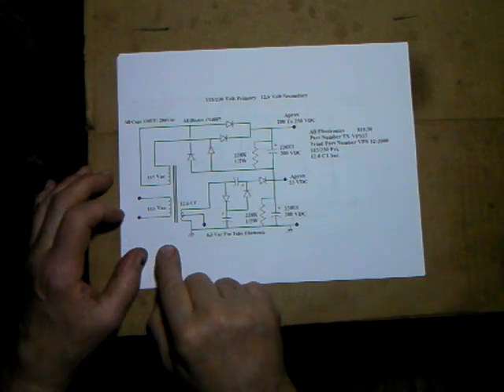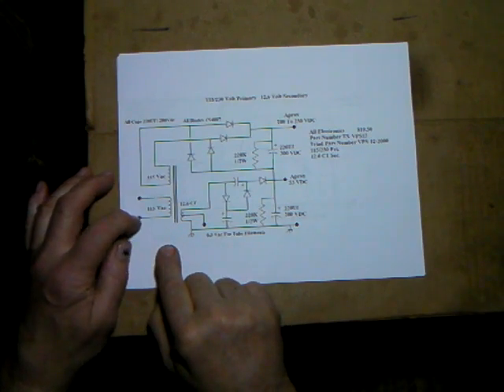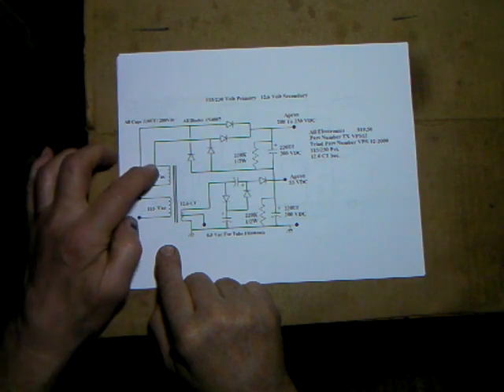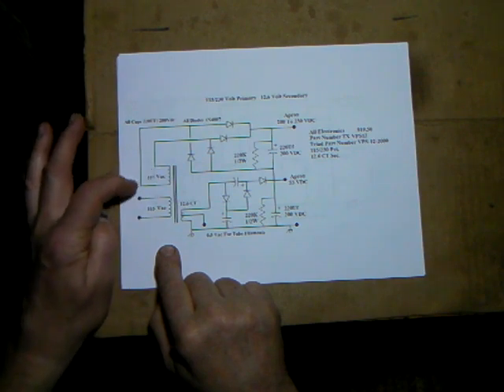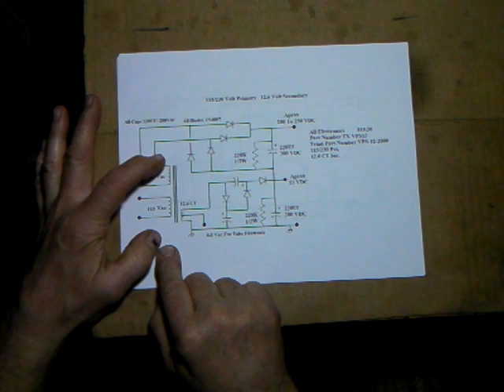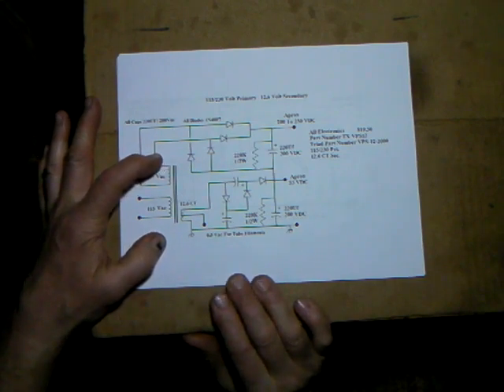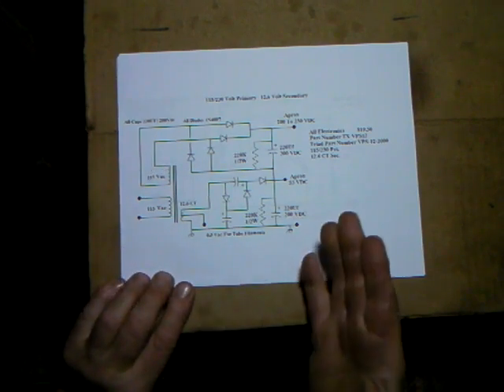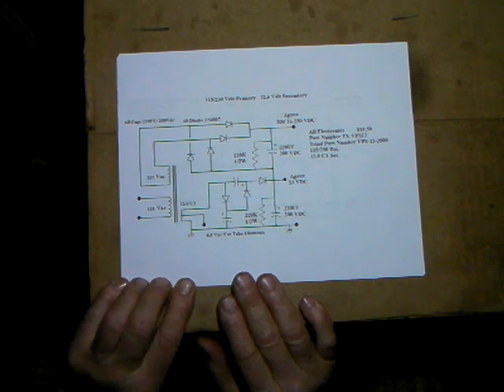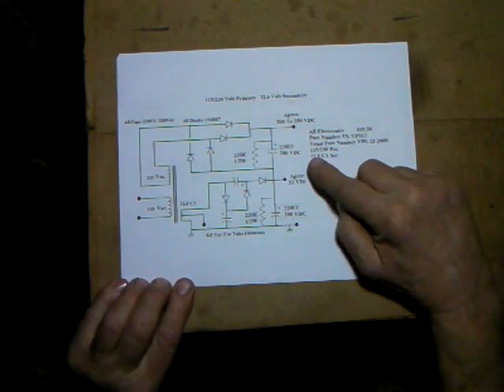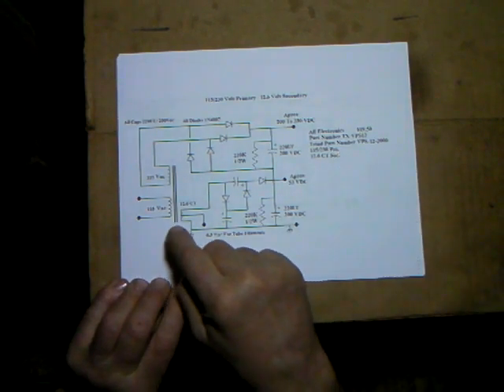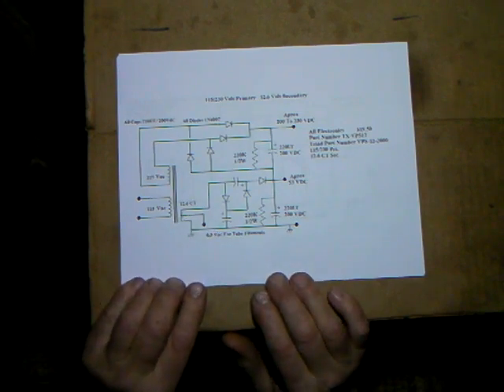This is an industrial transformer. It has two 115 volt primaries, and what this is for is so they can hook them in series and run this transformer at say 230 volt, or more commonly you hear of 120 or 240, but there still would be the same transformer.